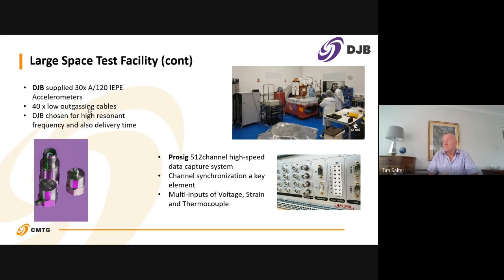And on the ProSig side, this was a 500 channel high-speed data acquisition system, which is just here. So this is the high-speed data acquisition system, which they wheel from room to room to do various testing, whether it's on the shakers as here, or whether it's in the shock test facility. The channels were a combination of voltage, also strain gauges and thermocouples. And a key element in the decision was our channel synchronization, where all 512 channels always had to be synchronized together within just one data point. So that's an aerospace type application.